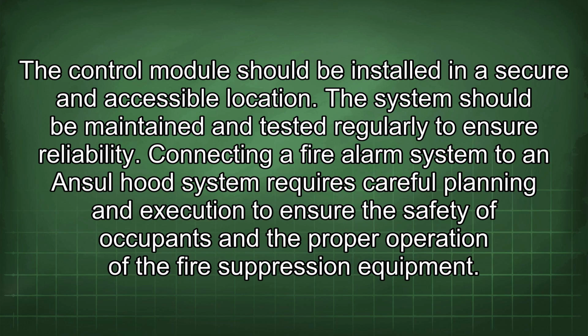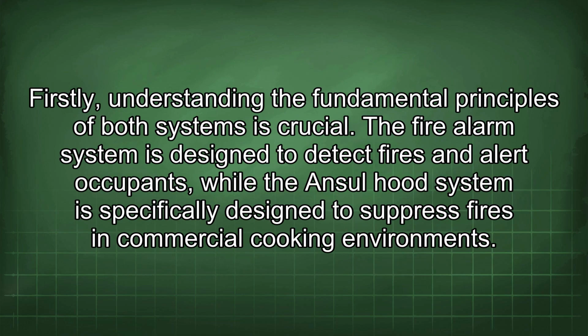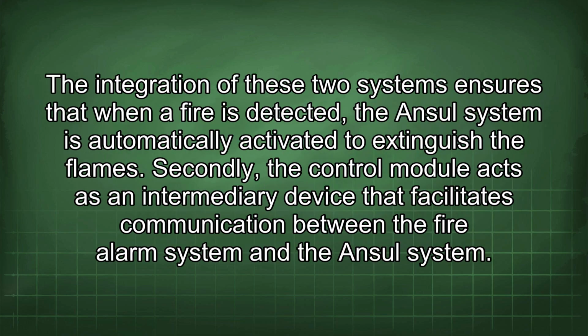Connecting a fire alarm system to an Ansul hood system requires careful planning and execution to ensure the safety of occupants and the proper operation of the fire suppression equipment. Firstly, understanding the fundamental principles of both systems is crucial. The fire alarm system is designed to detect fires and alert occupants, while the Ansul hood system is specifically designed to suppress fires in commercial cooking environments. The integration of these two systems ensures that when a fire is detected, the Ansul system is automatically activated to extinguish the flames.